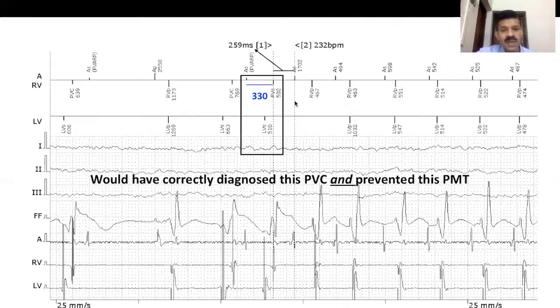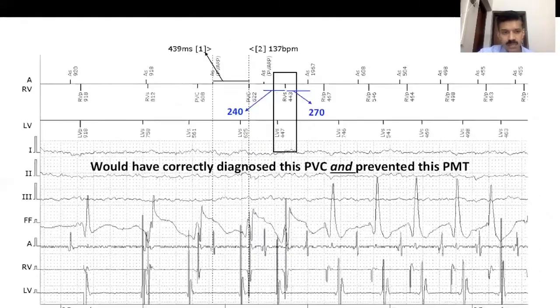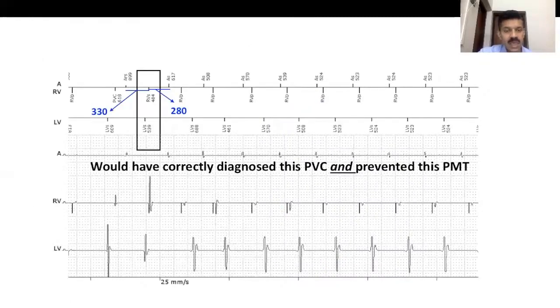This is another PVC PMT sequence from the same patient. AVA sequence with an AV delay of less than 350 milliseconds starting a PMT, but with an LV sense to RV sense sequence. It would have correctly diagnosed and prevented this one also. AVA sequence with an AV interval of less than 350 milliseconds, but an LV sense to RV sense sequence starting the PMT. It would have correctly diagnosed and prevented this also. AVA sequence, AV delay less than 350 milliseconds, but LV sense to RV sense sequence.